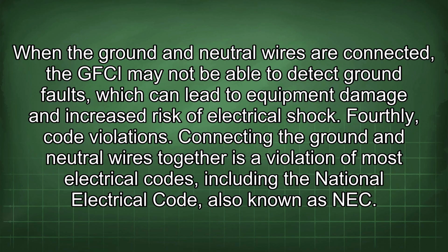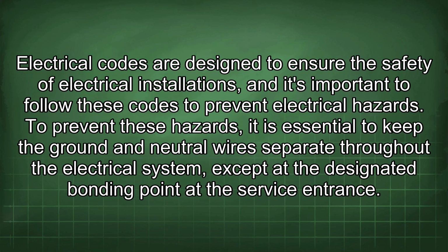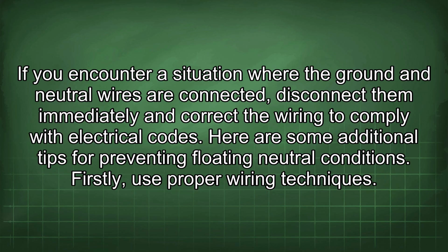Fourthly, code violations. Connecting the ground and neutral wires together is a violation of most electrical codes, including the National Electrical Code, also known as NEC. Electrical codes are designed to ensure the safety of electrical installations, and it's important to follow these codes to prevent electrical hazards. To prevent these hazards, it is essential to keep the ground and neutral wires separate throughout the electrical system except at the designated bonding point at the service entrance. If you encounter a situation where the ground and neutral wires are connected, disconnect them immediately and correct the wiring to comply with electrical codes.